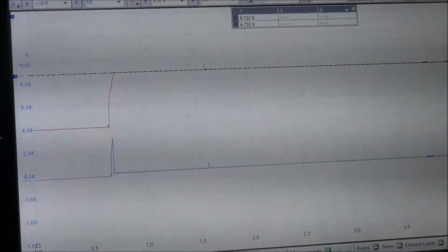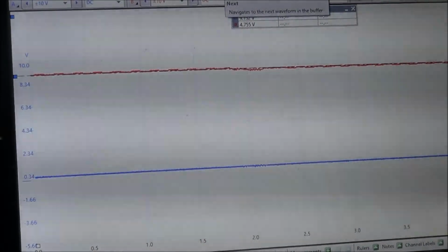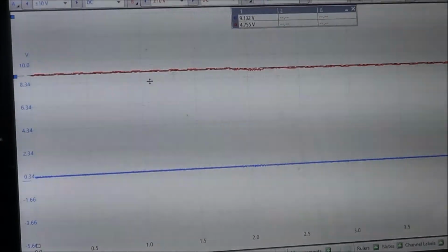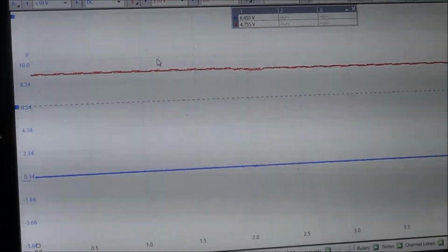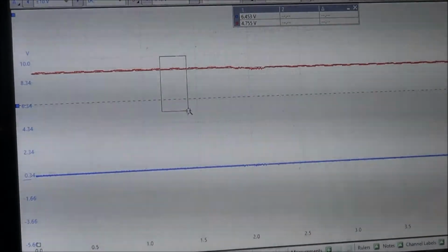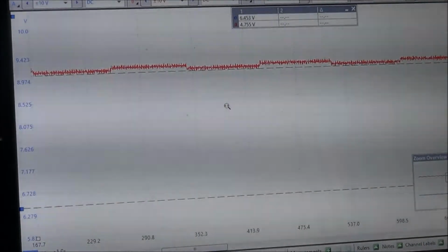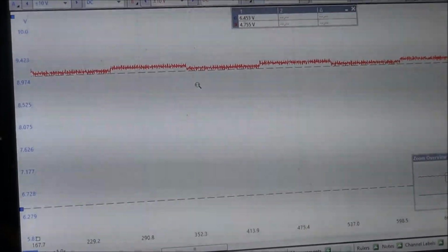The problem is, when we start it up, it should give out a signal. But right here, as you can see on this part, let's try to zoom in on this. See that part right here? Seems like right now we have an encoder bearing problem on this one.